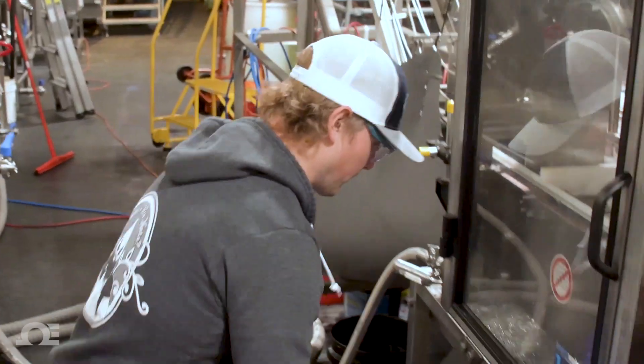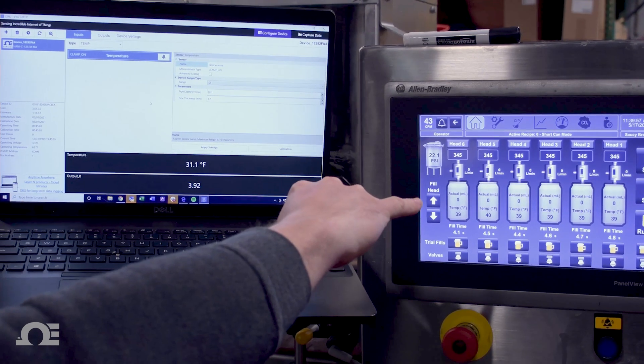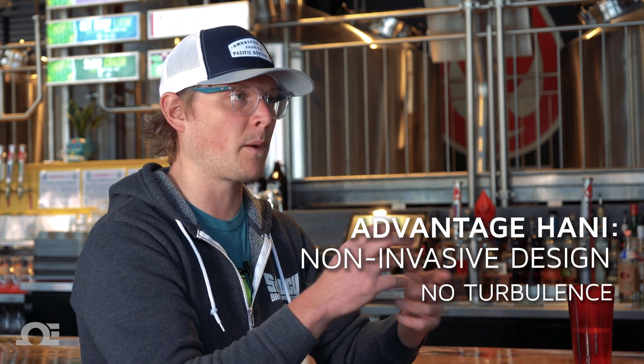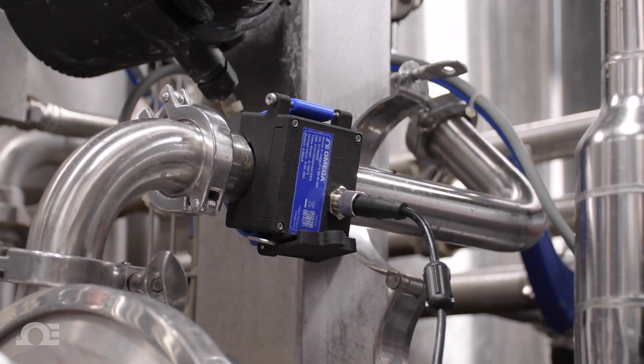It must be done cold. Anything above 32°F, and the closer you get to 41°F, it starts to get a little bit rowdy. By strapping the Hani sensor to the inlet of the incoming beer on the packaging line we're able to very accurately see how close we are to that 32 degrees Fahrenheit. My favorite part is that we're avoiding two potential pitfalls: one, turbulence with an invasive sensor that could cause disruption and decarbonation, and two, potential harbor for bacteria. With an invasive sensor, even with an inline instrument tee, there is still a spot where bacteria or mold could grow — even with a robust CIP cleaning system. Being on the outside of the pipe is not a problem.